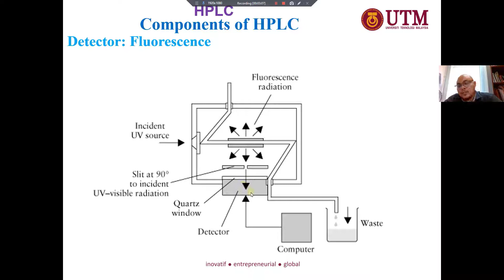Fluorescence detectors are among the most sensitive of the HPLC detectors, and depending on the compound, can be 10 to 1000 times more sensitive than UV detectors analyzing strong UV absorbing compounds. If the compound can fluoresce, usually the sensitivity is great compared to UV-vis analysis, but the compound must be able to fluoresce. If the compound cannot fluoresce, we submit it to the UV-vis detector only. But if it can fluoresce, it is better to use fluorescence HPLC, because the sensitivity for an analyte that can fluoresce is much higher with the fluorescence detector compared to UV-vis.